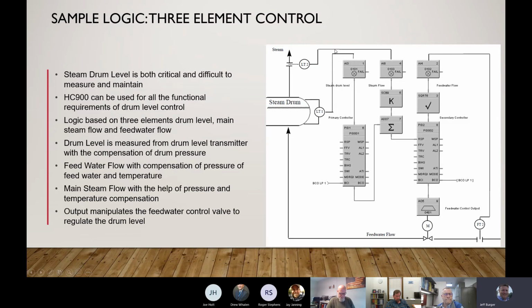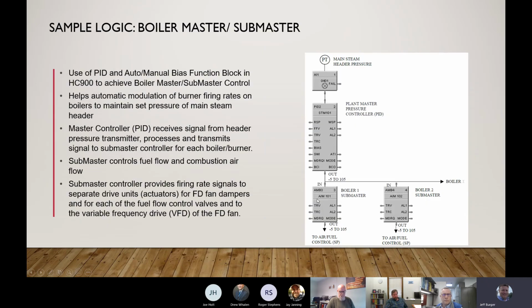So what's nice about this is that you can build this, save it into your library, and then the next time you want to do 3-element control, you would select it from the function block library, drag it out into your configuration, and literally within seconds you have a 3-element control system. So this obviously reduces a lot of engineering time with that function block library. The next application within boilers would be a boiler master or submaster. This would be where you have one plant master control system with the main steam header pressure controlling several different boilers and bringing the boilers on and off when needed. Also accomplishing your fuel-air ratio control down here on the bottom side of this architecture.